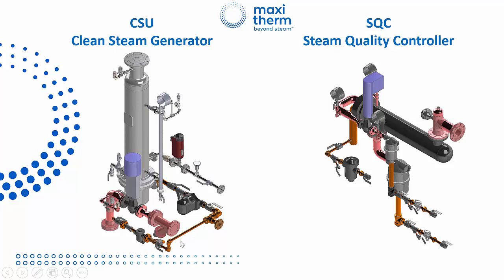Basically, you're coming in here with steam pressure from the boiler room. We're going into the tubes like this, coming out here. Clean steam, clean water, so bring us RO water. We're going to make you RO steam outlet here. And since the bundle is a U-tube bundle, there's a hotspot right there generating really dry, quality steam. The steam quality controller is more for sterilization processes, to avoid any wet packs in the process. We deliver really high quality steam.